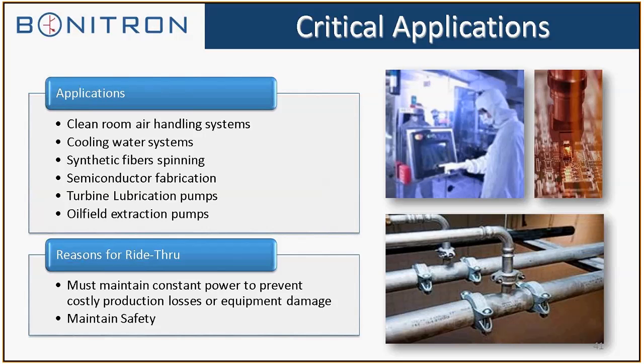So you have to keep that constant lube oil flow to the turbine to keep it lubricated so it doesn't overheat. There are a lot of applications out there that have to have consistent lubrication oil, airflow, or chill water flow, and they can't have any deviation. Those are the applications you look for when specifying this stuff. And of course, you weigh the cost of the downtime and product damage against the cost of the ride-through.